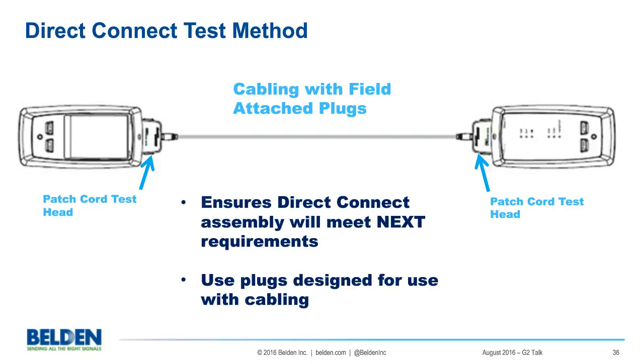So if you have a tester that can perform this test, you would set it up in this configuration, where we have a patch cord test head on each of the main and the remote units, and then in the middle is the direct connect assembly that had field attached plugs on each end. And then you would test it, and this would ensure that your direct connect assembly will meet the NEXT requirements. It's very important to remember that the plugs must be designed for use with your cabling.